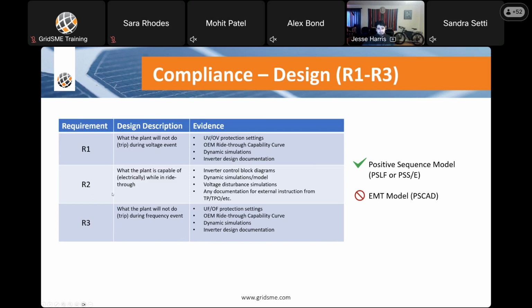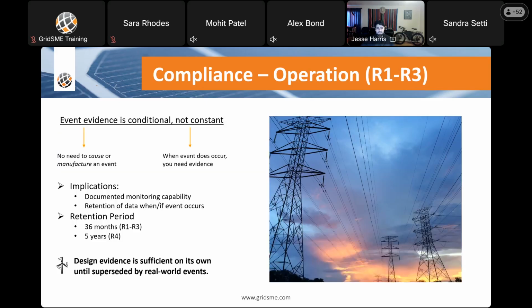And then R2, remember this is that performance-based standard. So what the plant is capable of electrically while riding through. And evidence for this can include inverter control block diagrams, dynamic simulations and models, voltage disturbance simulations, and any documentation for external equipment. For this, NERC has made it very clear that no EMT model is necessary, but you can have positive sequence models such as PSLF or PSSE, and those will be sufficient. So that was the design for R1 through R3.